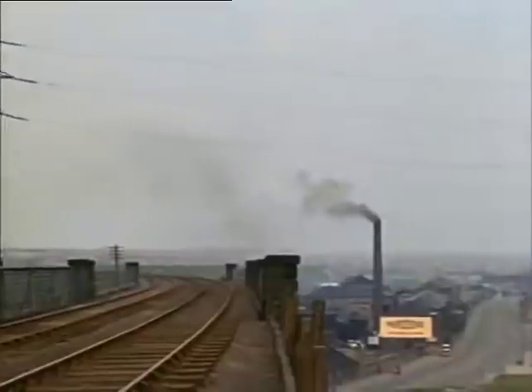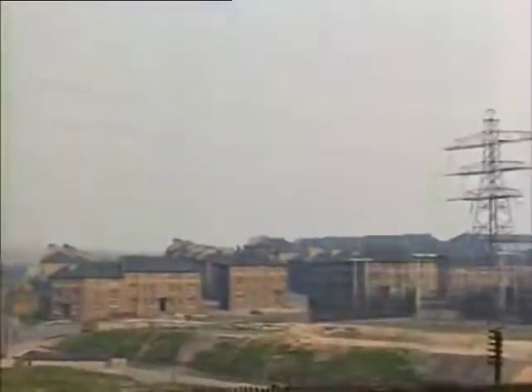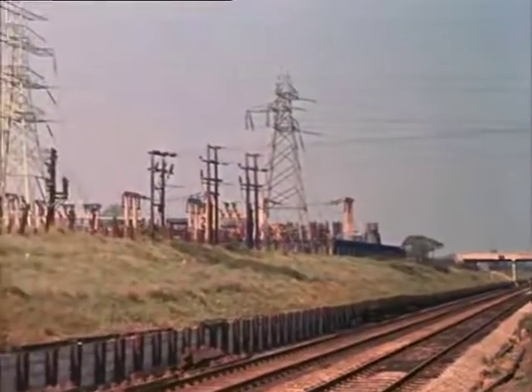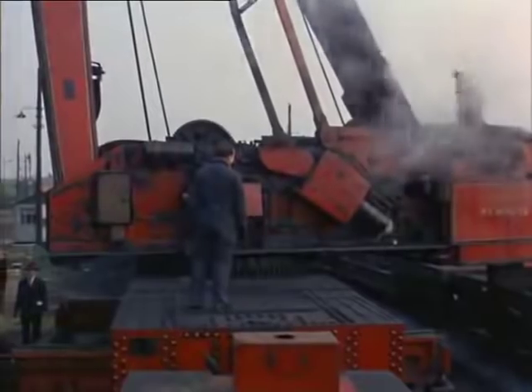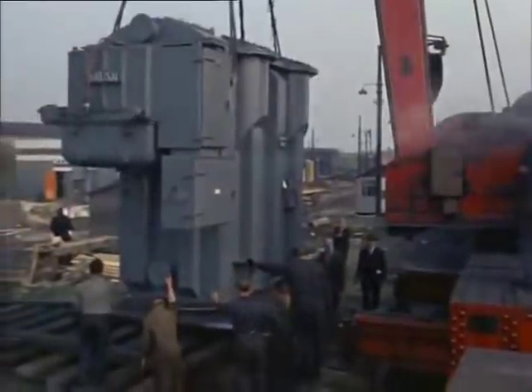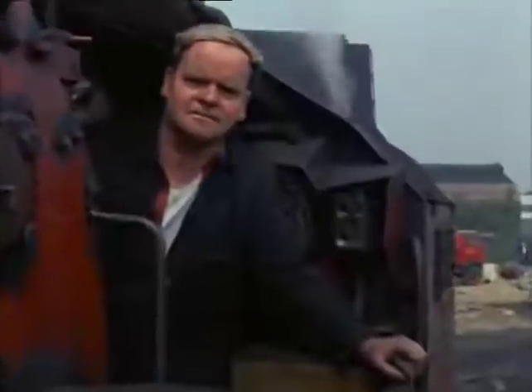Usually, towns which the railway serves are also supplied with power from the grid, so there will be many places where grid substations are close to the line. At the substations, the grid's 132 kilovolt bulk supply is transformed down and fed to the railway at the required 25 kV. The transformers belong to the Central Electricity Generating Board, but in some places, as here at Acton Lane, where they have had to be specially installed, the railway has carried out the installation.